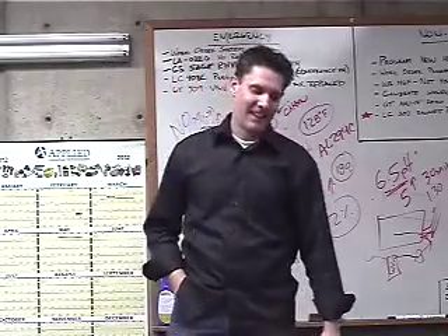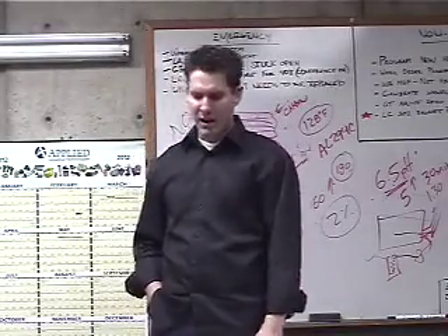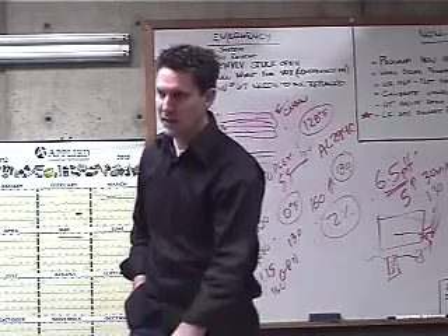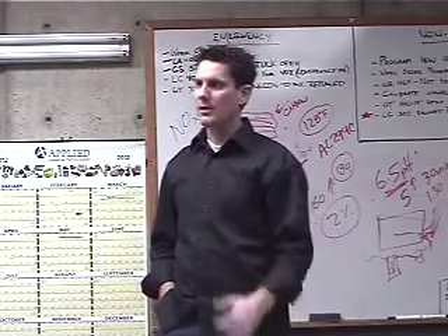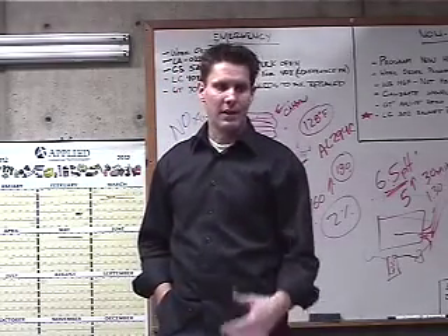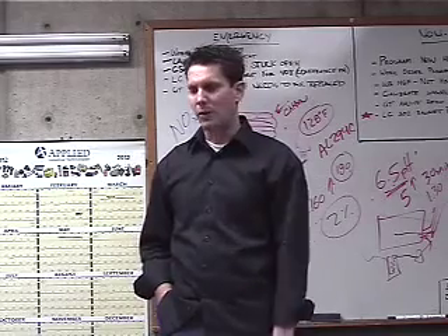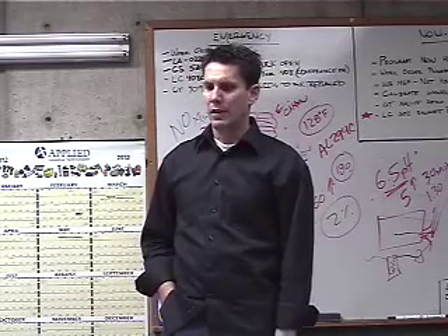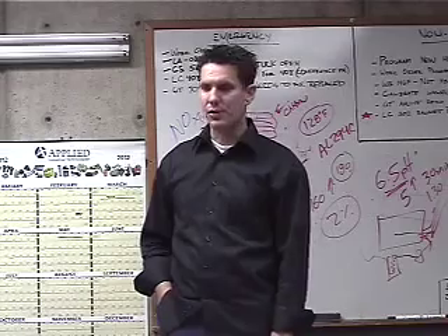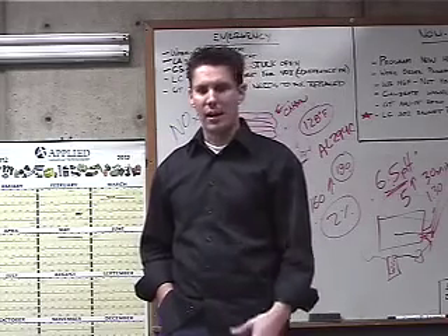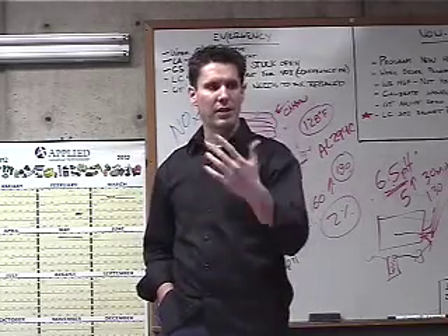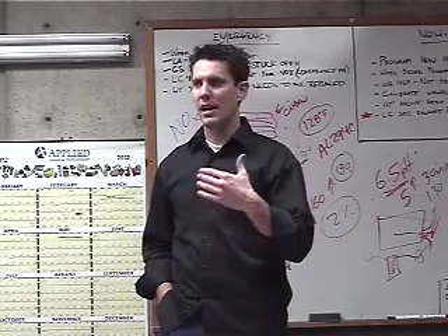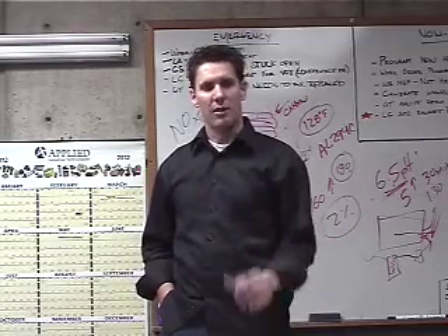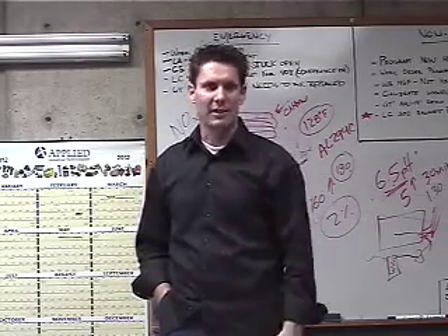You know what? I'll be honest with you, no matter how much we stand up here and say maintenance, maintenance, maintenance, half the jobs we do this on, they never maintain. We might get a call 5-6 years from now, and hey, the boiler's chugging out, it's tripping out on flame failure. So we go out and, yeah, it's got soot in it, so the boiler requires some cleaning. But usually it's not detrimental on the boiler. But I don't want to say that, well, I guess it's not on camera.